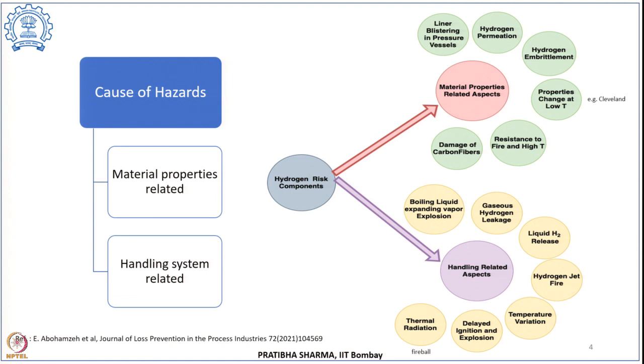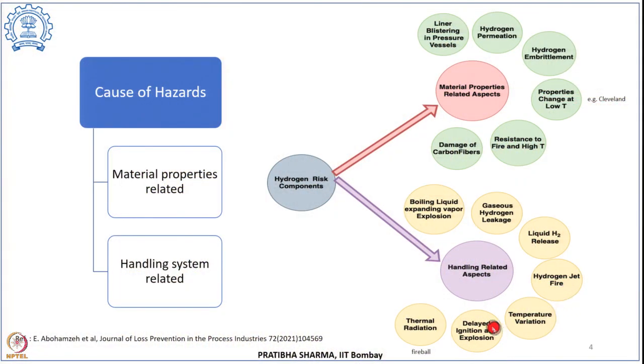A hydrogen jet fire is a high-velocity turbulent flame arising from combustion of a hydrogen-air mixture in the flammable range, released with very high momentum in a certain direction, which can lead to property damage and several injuries. If instead there is a delayed ignition after the gaseous hydrogen leakage, hydrogen gets time to mix with air, and then if an ignition source is present it can result in an explosion.